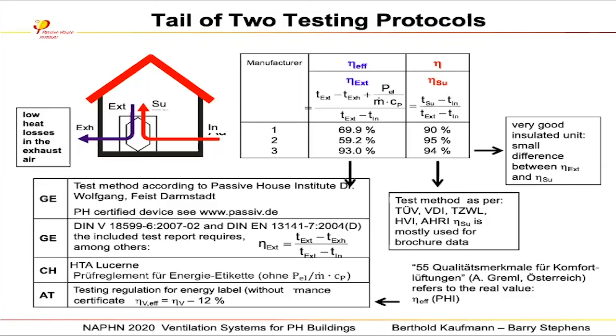One of the most critical things when we're looking at Passive House projects, and if you're using the Passive House Planning Package for your energy model, is this chart, which shows 3 different HRVs that were tested to both standards. On the left, the blue column, excuse me, that's Passive House. The blue is about 70%, 60%, and 93%. The North American method has those at 90, 95, and 94%. So if you plug in 90% into your PHPP and it's actually 70%, you've got a big problem. You're going to have a very different actual energy demand than what you had planned on. So this is really critical.